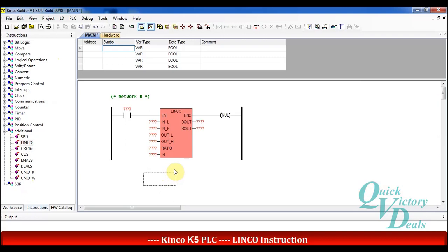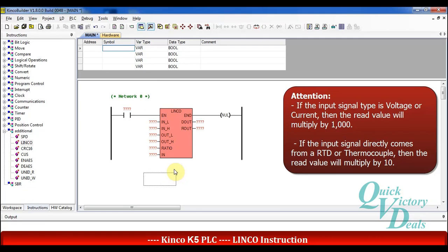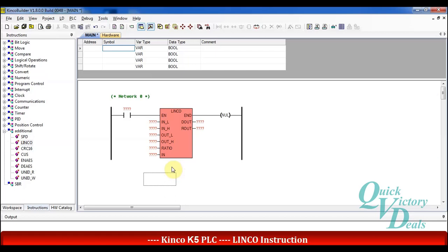In Kinco CPUs, if the analog signal is a voltage or current signal, the read value is multiplied by 1000. And if the analog signal is from an RTD or thermocouple, the read value in the CPU is multiplied by 10. So we will use the LINCO function as a linear conversion to reach the correct value for analog signals.